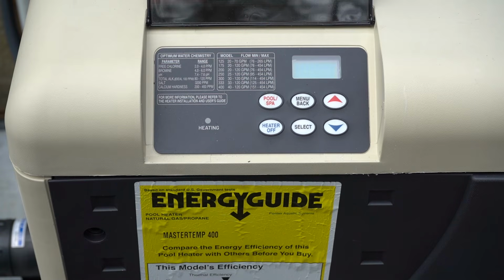Most professionals, when they install these heaters, will check the actual gas regulator, and if the gas regulator gets too high or too low, then the heater actually will not fire. It will lock it out. And you'll have some type of ignition failure associated with that. But if the gas valve is not adjusted properly on the manifold side, then it will cause the flame to either be too rich or too lean, and either one of those is going to cause a problem. So we're going to go ahead and we're going to change this heat exchanger, which is going to be in another video. And then after we change this heat exchanger, we're going to go in and we're going to adjust the gas valve and the manifold side of the gas valve, and we'll show you how to properly do that as well. So that's it for this video.